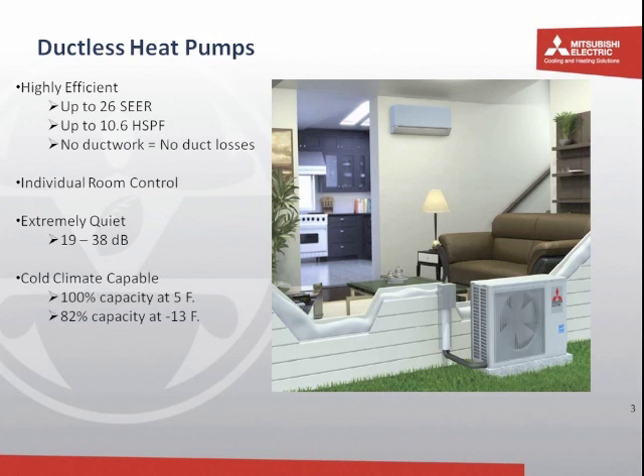We also are going to be talking in further detail, but the systems are cold climate capable, a capability you don't often think about when you're talking about heat pumps. Systems that we'll be covering in some detail are capable of producing their rated heating capacities at 5 degrees Fahrenheit outdoors, and all the way down to negative 13 degrees Fahrenheit are still producing 82% of their rated capacity. Again, a great fit in a passive house design where you've eliminated almost all of the heat loss. The little bit that remains can now be treated very effectively with a super efficient heat pump. So that's the basic ductless heat pump or mini split.